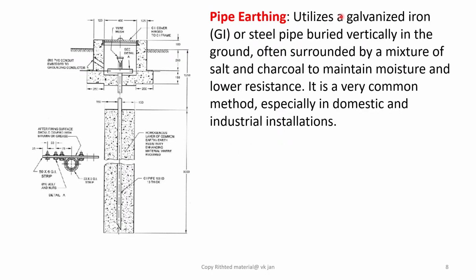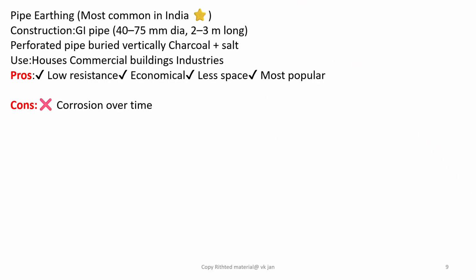Pipe earthing utilizes a galvanized iron or steel pipe buried vertically in the ground, often surrounded by a mixture of salt and charcoal to maintain moisture and lower resistance. It is very common method, especially in domestic and industrial installations. Some features of pipe earthing. Pipe earthing is most common in India. Construction: it uses GI pipe of 40 to 75 diameter and 2 to 3 meter long. Perforated pipe buried vertically and surrounded with charcoal and salt method.